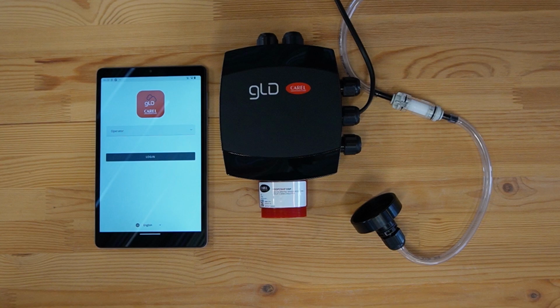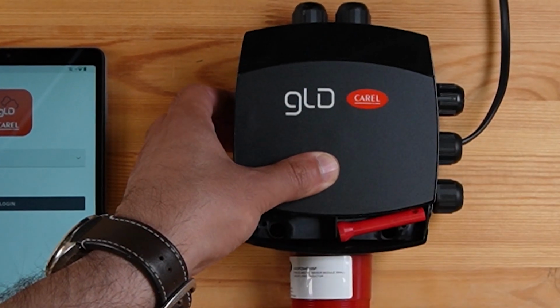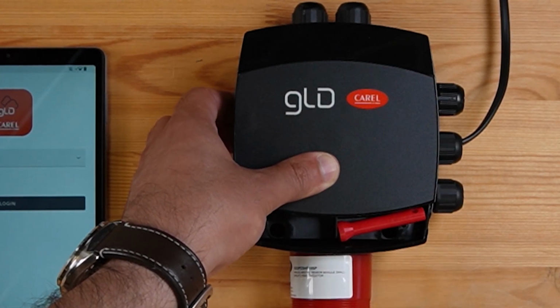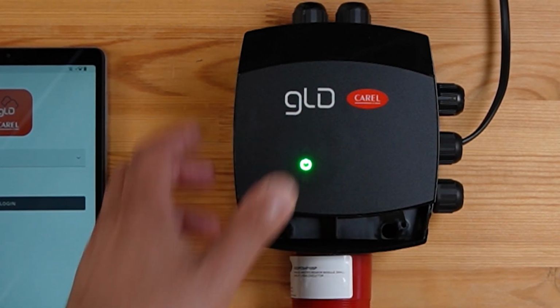We recommend that the unit has been in operation for a minimum of 45 minutes before conducting this procedure to ensure that the sensor is calibrated correctly. Let's have a look at how easily this can be done. First, let's put the unit into service mode. This is done using the magnetic wand you will find under the bottom lid.